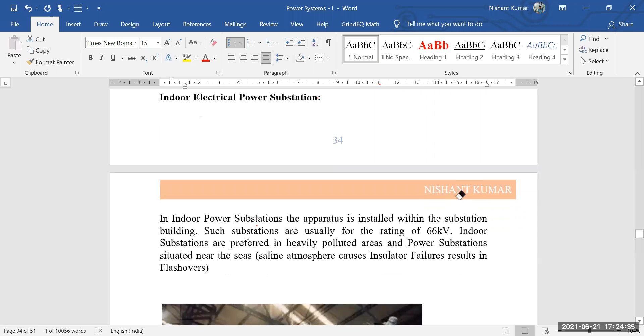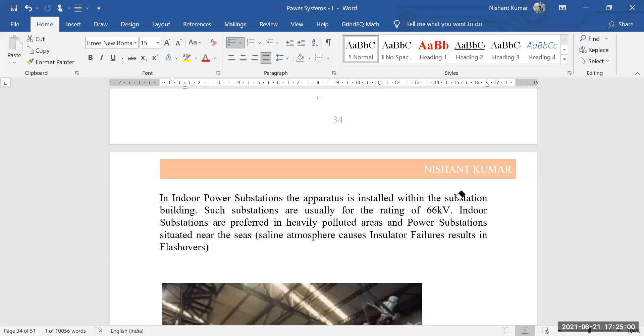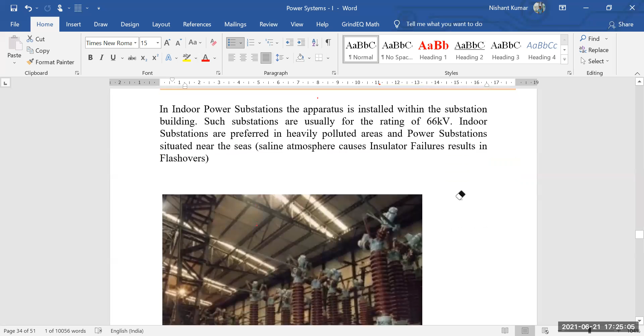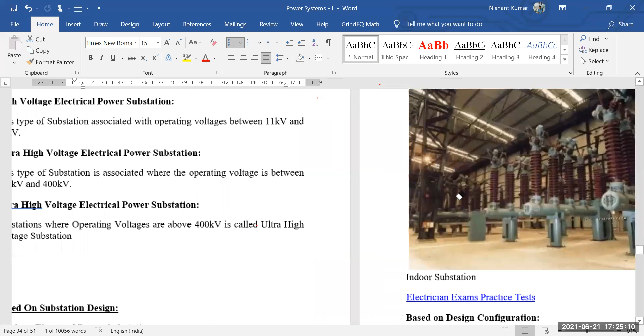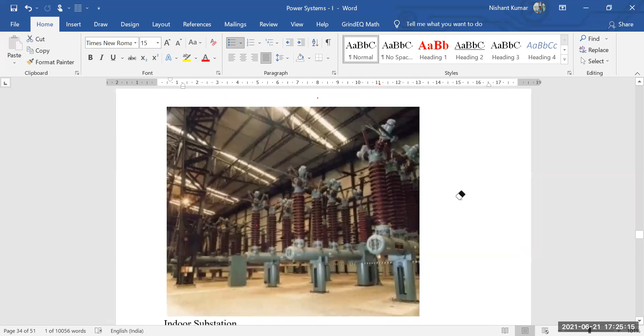Indoor substations are preferred in heavily polluted areas and power substations situated near the sea — because, as written, the saline atmosphere causes insulator failure resulting in flashover. So this is the segment where nearest to the sea you will find indoor substations. This is one picture of your indoor substation, this is how it looks.